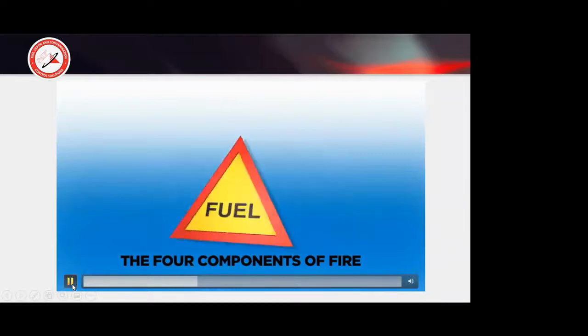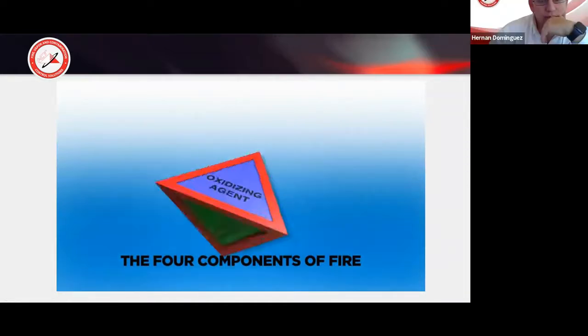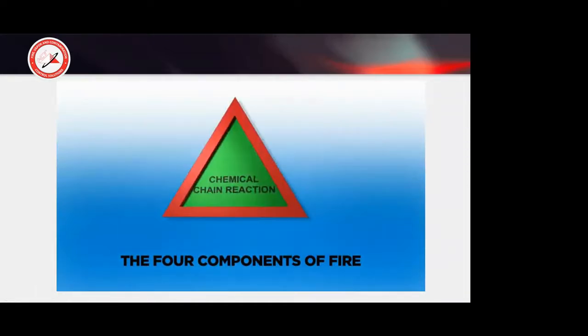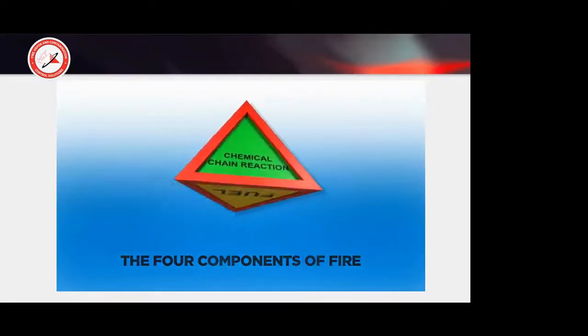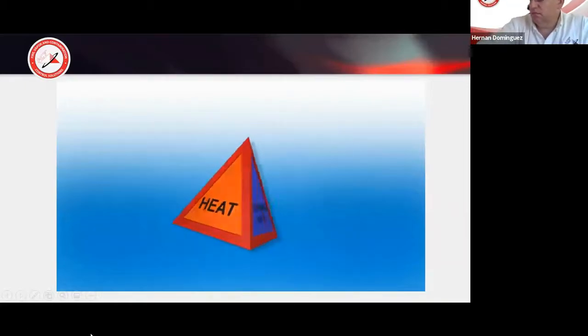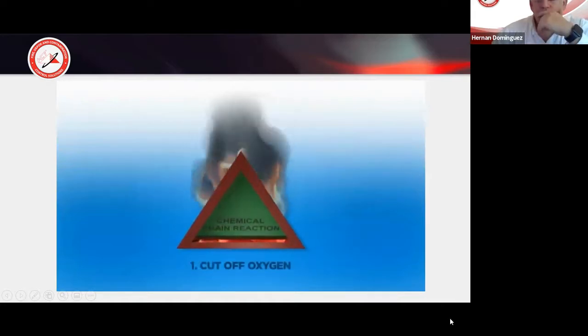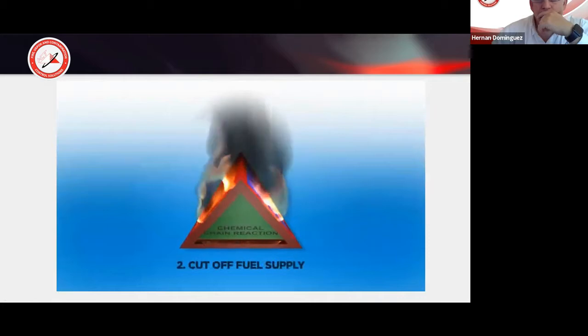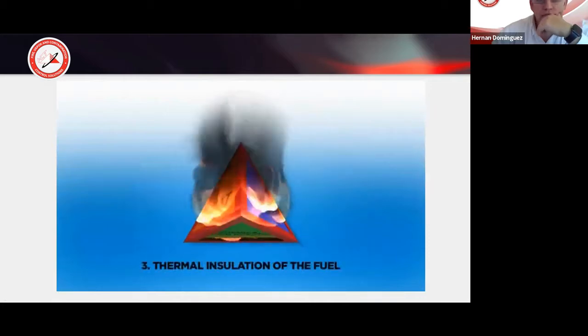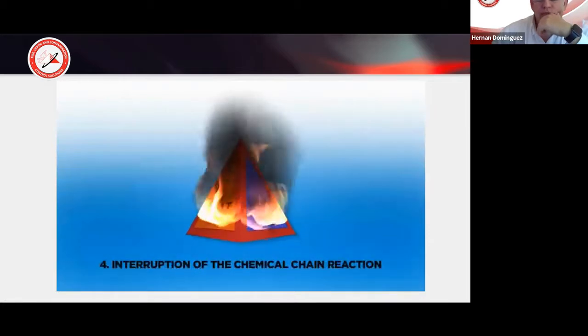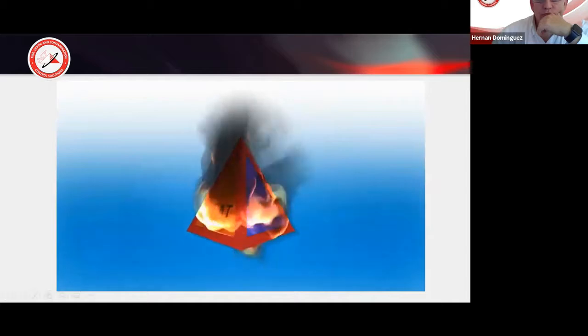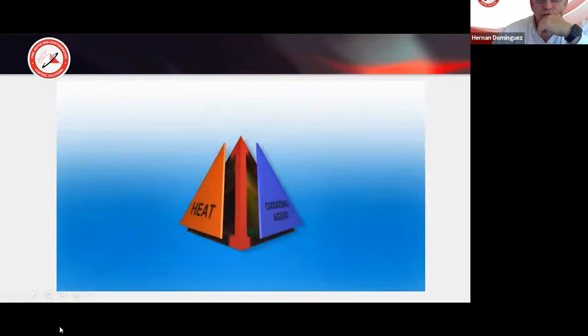Fuel, oxidizing agent, and the chemical chain reaction. If one or more of these components are absent, a fire cannot occur. When all four components are present, heat, fuel, oxidizing agent, and the chemical chain reaction, fire will occur. There are four options for extinguishment: cut off oxygen, cut off fuel supply, thermal insulation of the fuel, and interruption of the chemical chain reaction. When one or more of the components are removed, the flame goes out.